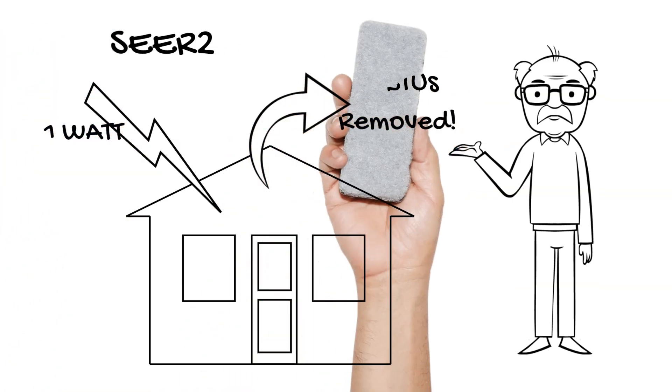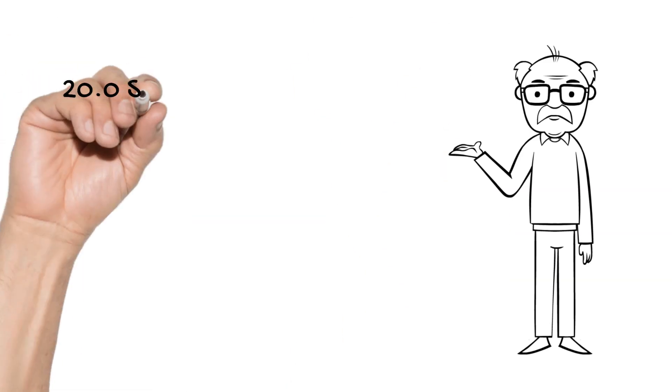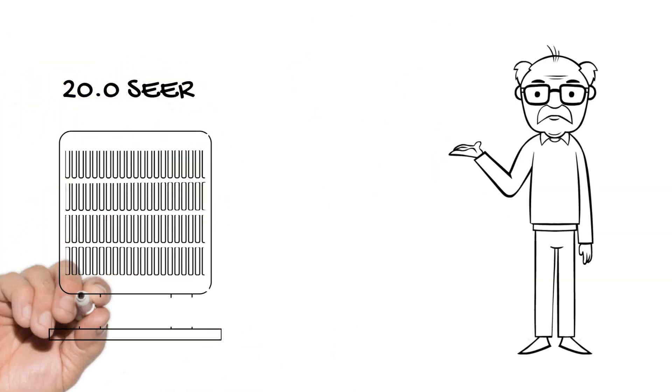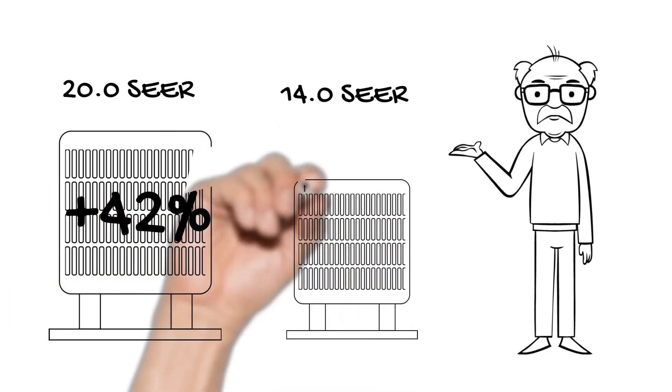Thus, if you have a 20.0 SEER2 unit, 20 BTUs would be removed per watt of power. That makes a 20.0 SEER2 unit 42% more efficient than the 14.0 SEER2 model.